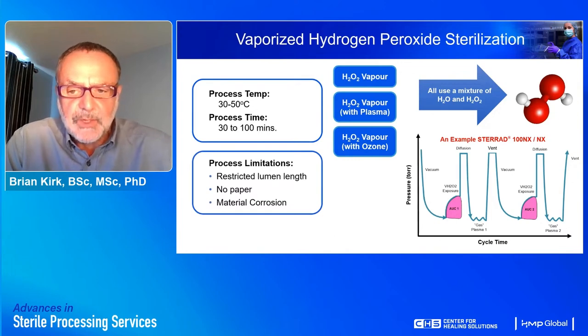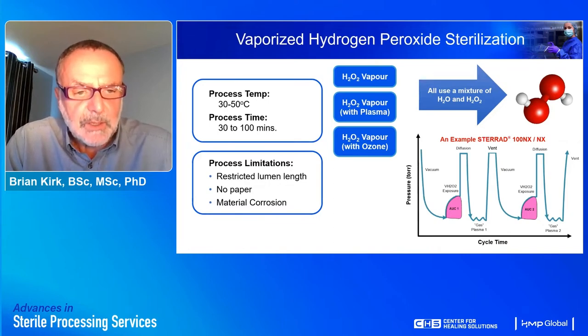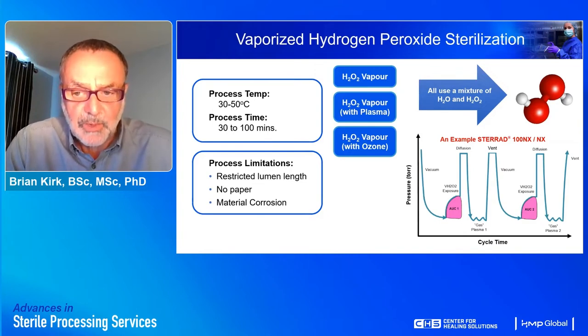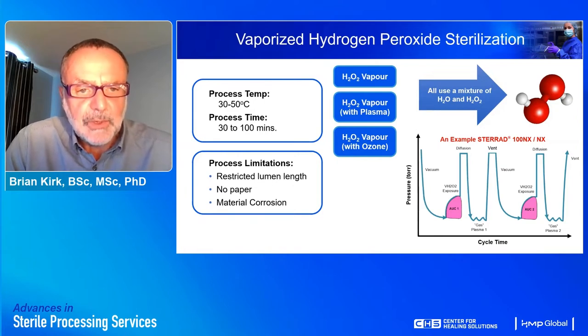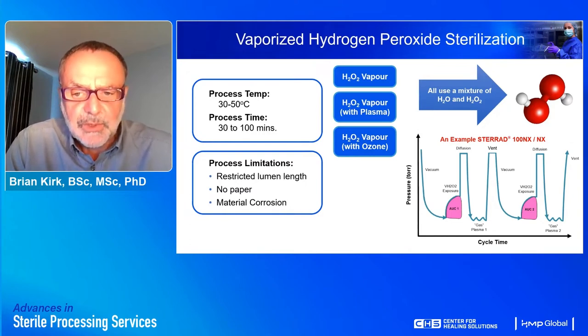These hydrogen peroxide processes have limitations such as restrictions on the length and width of lumened instruments that can be sterilized, and some packaging will inactivate the hydrogen peroxide vapor — so cellulosic materials should be excluded and more specialized packaging such as Tyvek-type is recommended. Plasma can be used either at the end of the exposure stage to inactivate hydrogen peroxide and make emissions non-toxic, or at the beginning to preheat the load prior to introduction of the vapor.